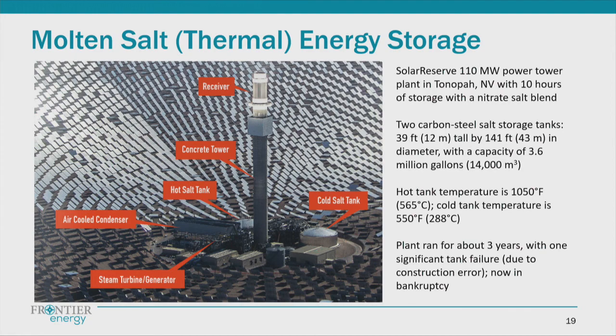And so this is a power plant in Nevada with the power tower, the focus mirrors on the glowing white hot receiver. For this particular plant, the salt is the heat transfer medium and the storage medium. And then you've got steam cycle generation down below. That's a standard power industry, high pressure steam turbine inlet temperature. And so even their cold tank is still hot because you don't want it to solidify. You always keep it in liquid form. It works. Salt works. Salt's relatively expensive, but it's stable. You don't have to have a purge stream and a makeup stream, as long as you don't overheat it.